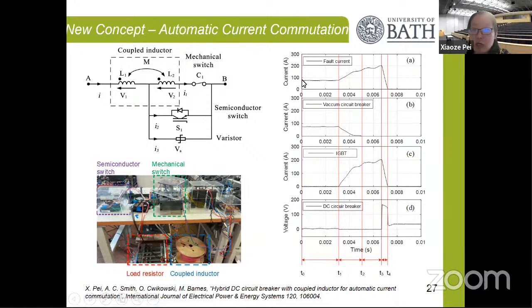And these are some of the interesting results. You can see this is a normal operating current, and the current goes through the mechanical switch. Once we create a fault, you can see the current start to increase. This increase of the current couples those 2 inductors together and drives the current out of the mechanical switch. The mechanical switch can then be turned off at the zero current here, and the current will be interrupted by the semiconductor switch after this. This is the structure we proposed, and the key advantage is that it has automatic current commutation in the fault condition, which means we rely less on detection of the fault in the circuit.